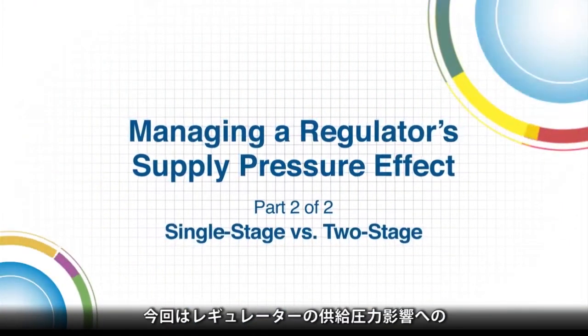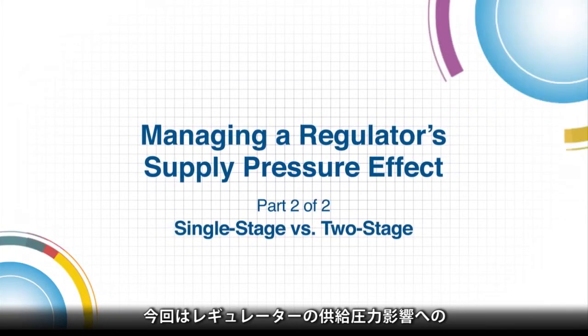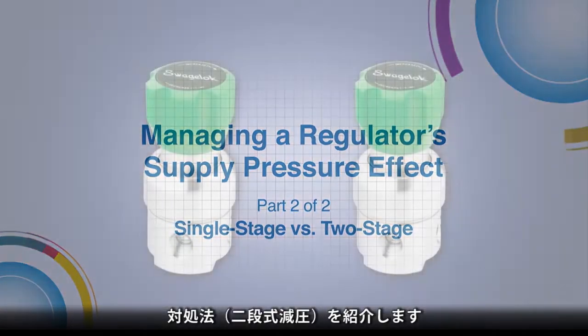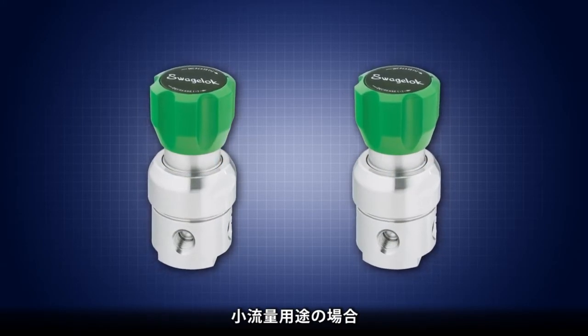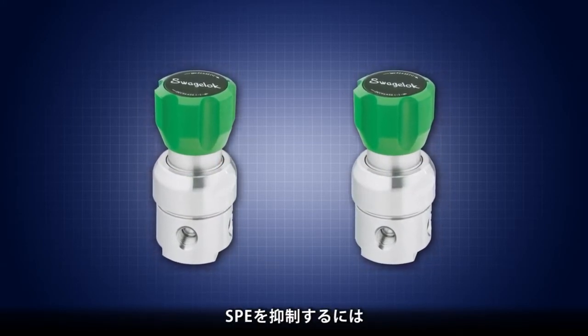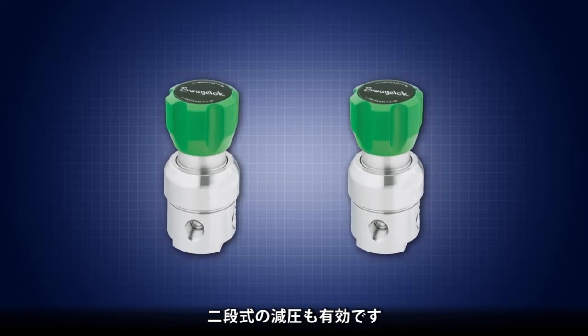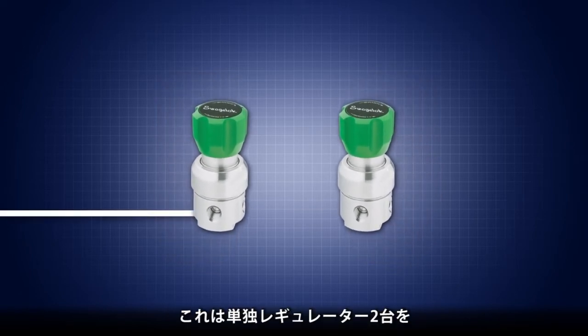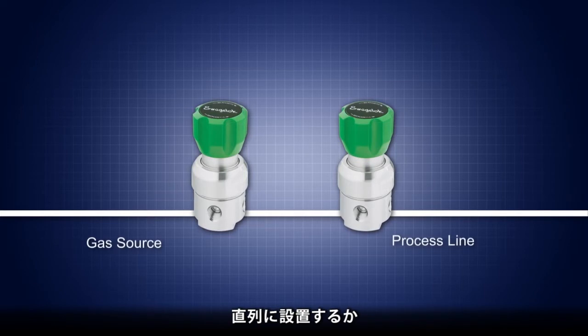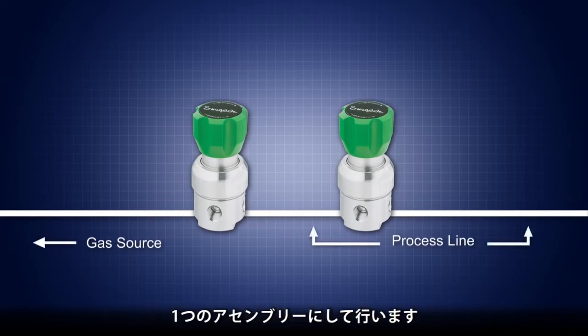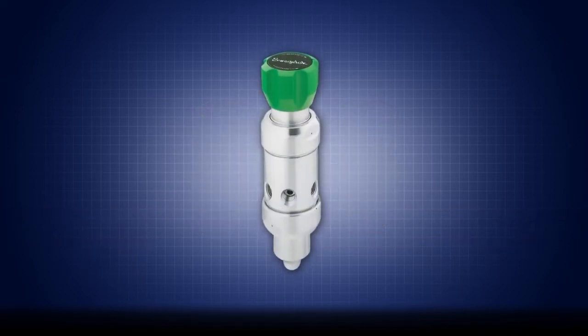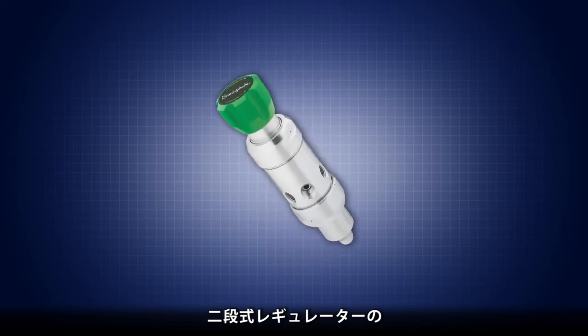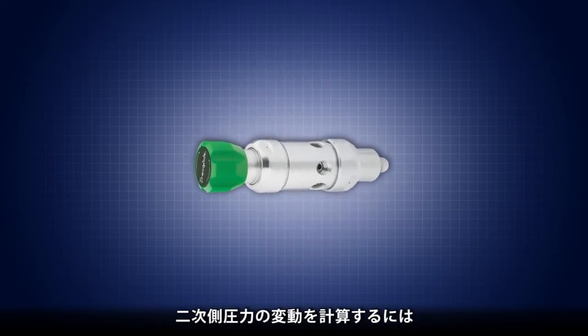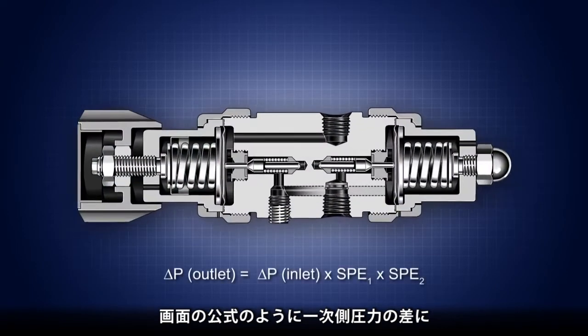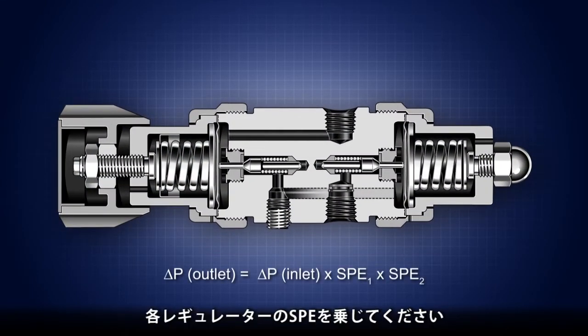Today's topic is considerations in managing the supply pressure effect of a regulator. For lower flow applications, an alternative method of regulating supply pressure effect is to use two-stage pressure reduction. This can be accomplished by using two single-stage regulators installed in series, or the two regulators may be combined into one assembly. To calculate the variability of outlet pressure for a two-stage regulator setup, the inlet pressure difference is multiplied by the SPE of each regulator, as illustrated in the following equation.